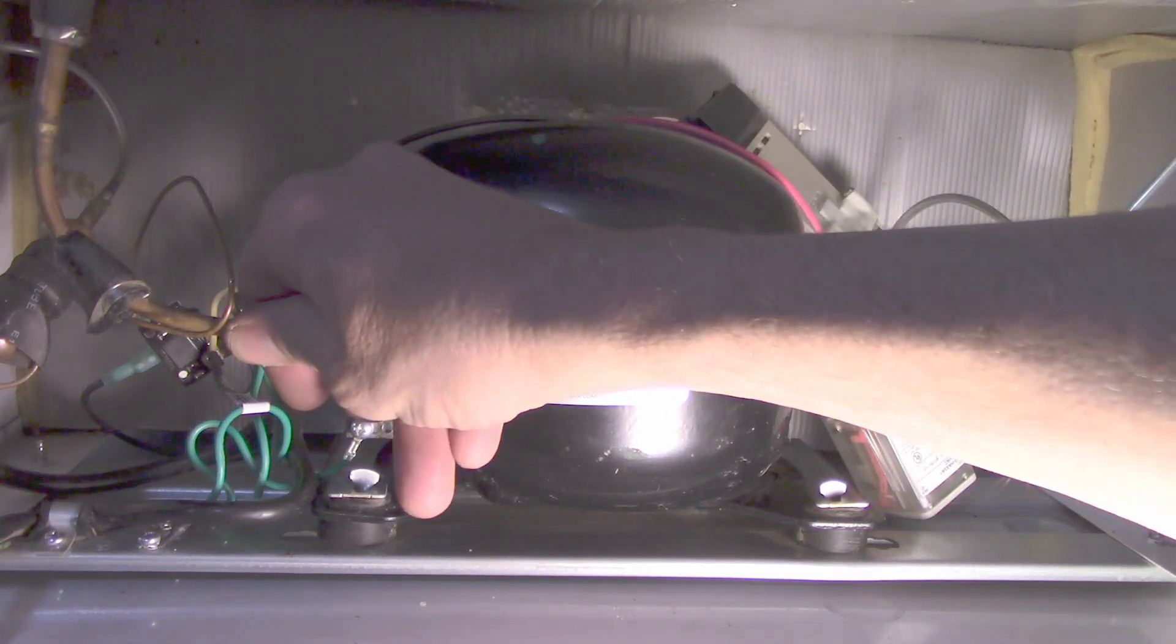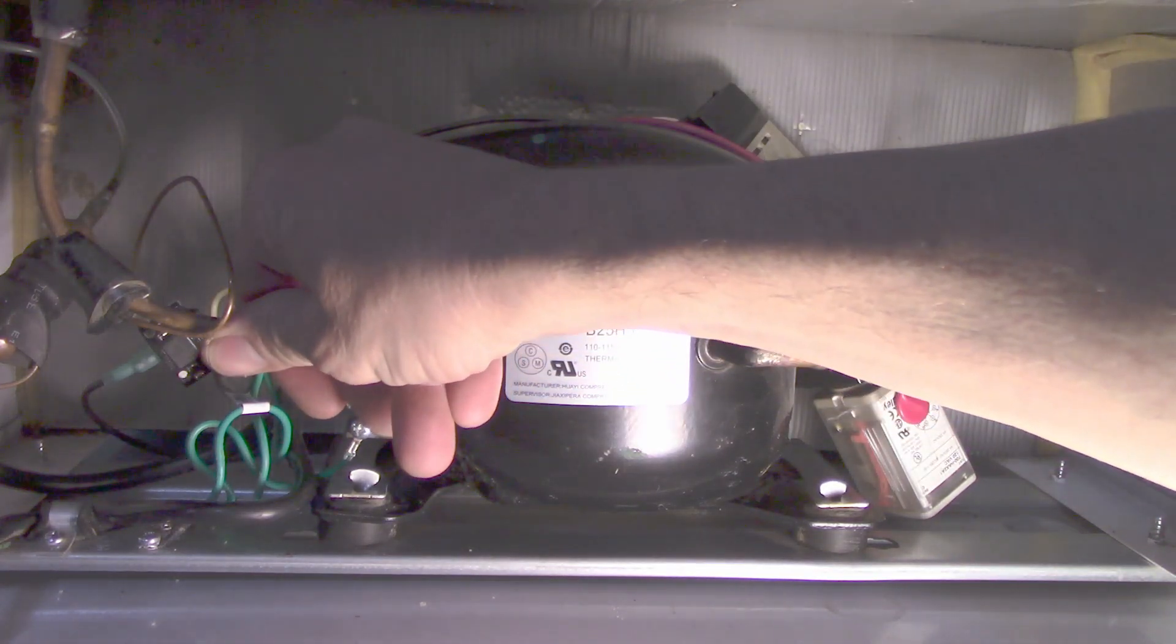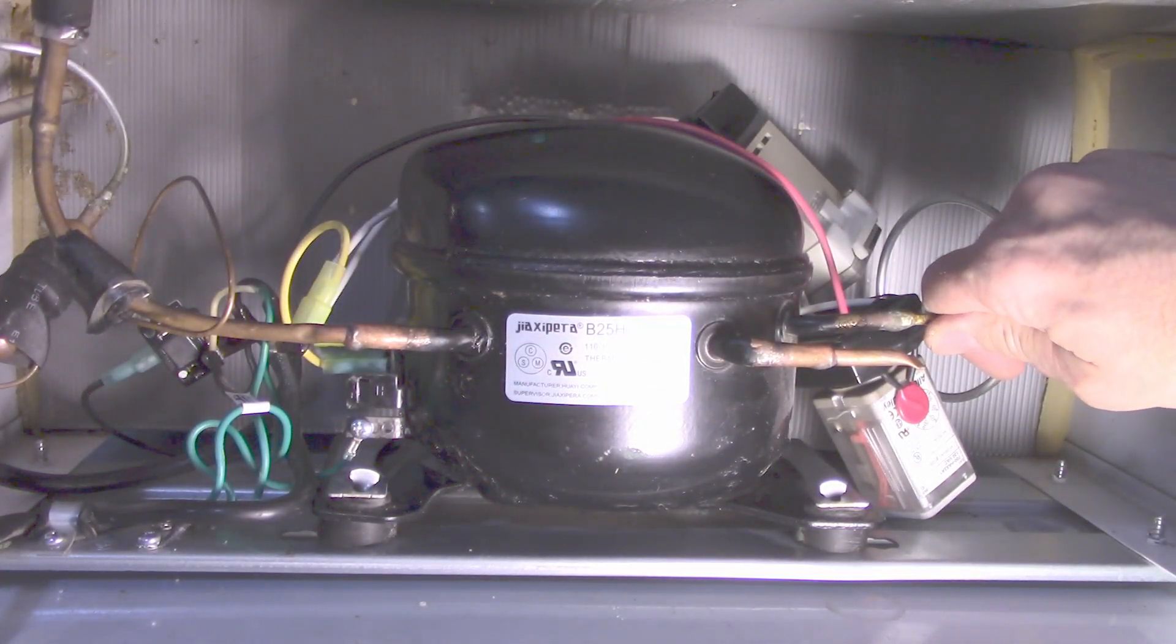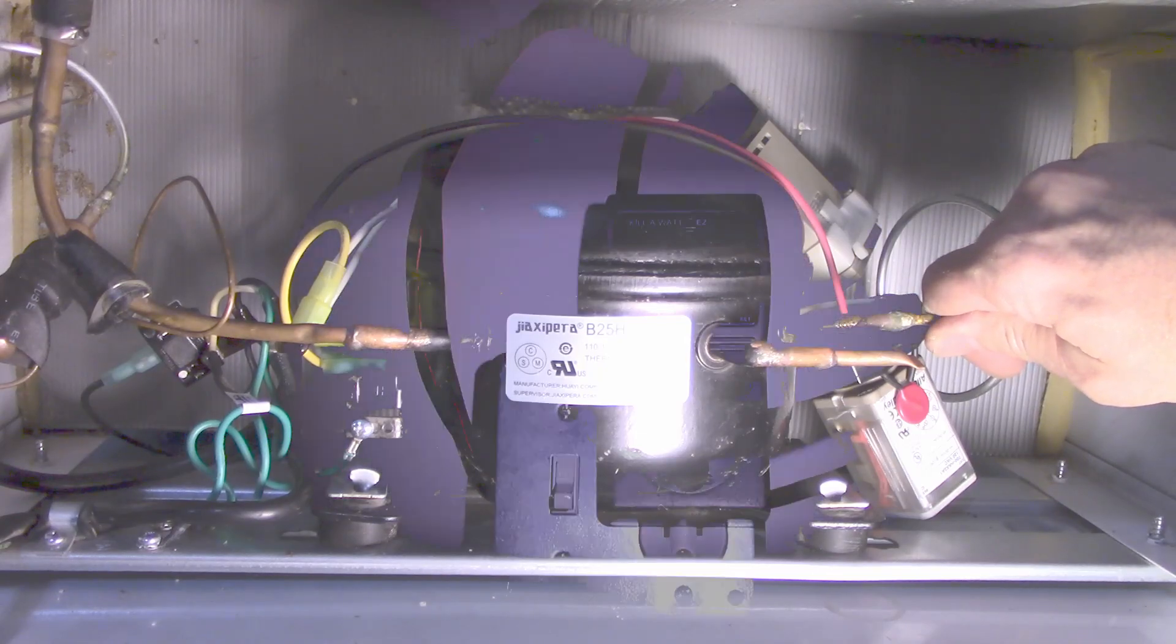So all we had to do was supply power to the compressor on the start side for about a third of a second until we could get the compressor up and spinning. I hear it running. Let's see if we're getting any temperature change. Oh yeah, we're getting some cool over here on the suction side, and the high side is definitely getting warm. We're generating heat.